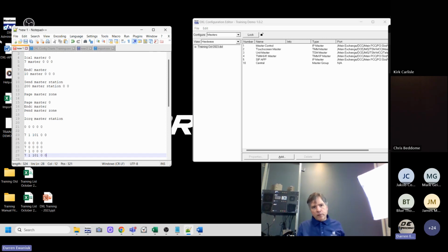And then that finally becomes a valid command. Now, how our system handles the processing of the command is that it processes the command when the first register changes. So this line right here that I'm highlighting, the first register changed from a 0 to a 7, or it was written. The value was written. It doesn't even have to be changed. It could have had a 7 previously and you write a 7, but the system knows that you wrote something in. Even if it's the same value, it will act on it because you wrote something into that register.